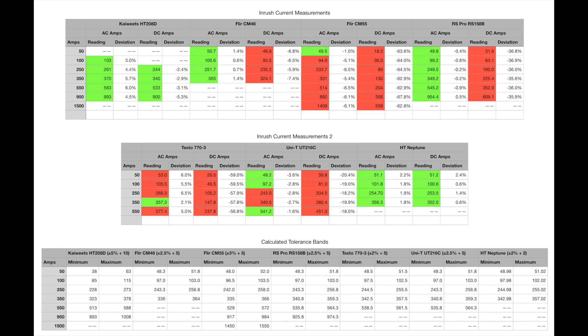The Flir CM46 shows good AC amp readings; DC amps are a little out — up to 8% low — but fairly respectable and reasonably consistent across the range, though limited to 400 amps. For the Flir CM55, almost all readings are out of specification apart from the very first AC measurement — I'm not sure what's happening with that unit and it needs further investigation.